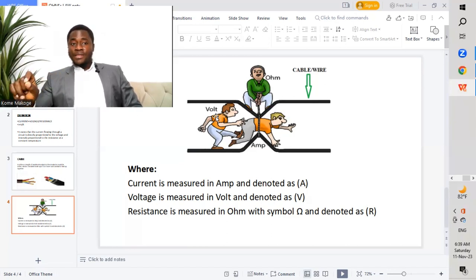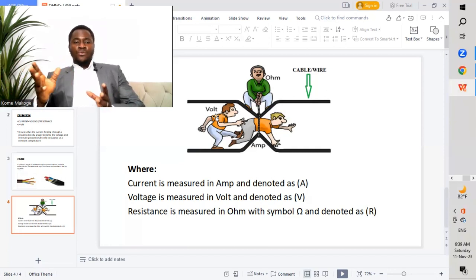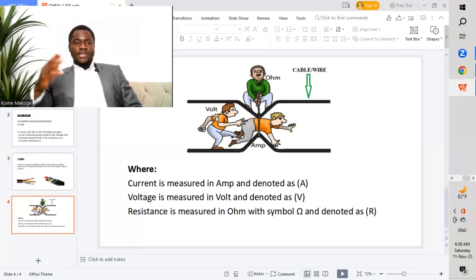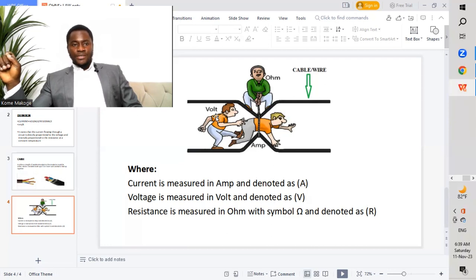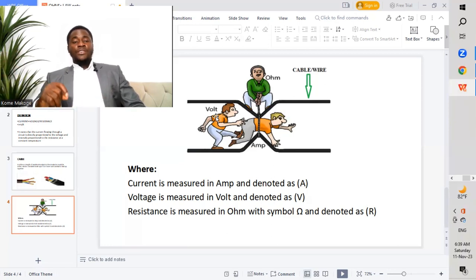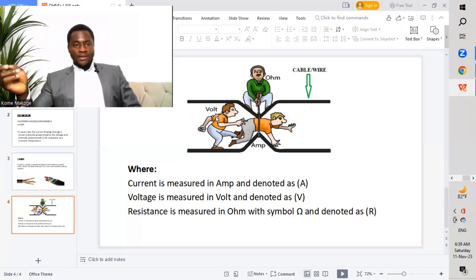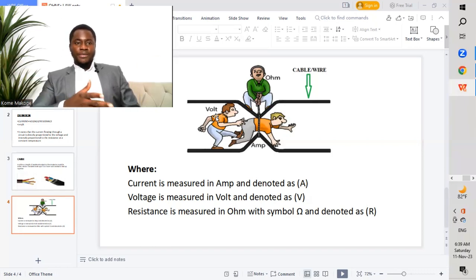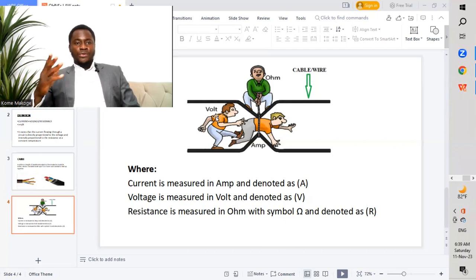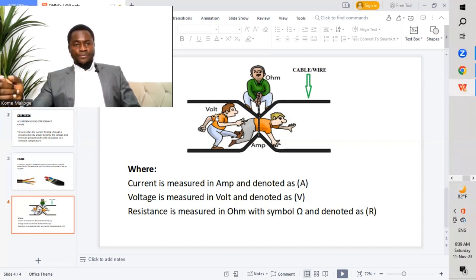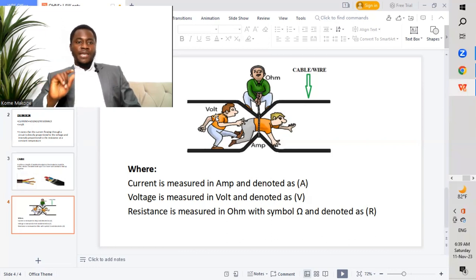Abnormality in a circuit comes in when we have a temperature rise. If you go through different cable manufacturers' catalogs, you will see different temperature ranges — either 70 degrees C or 90 degrees C. These different temperatures are taken into consideration when selecting a cable size. For example, when selecting armored cables, we might be working with 70 degrees C and we go through the appropriate column for that temperature range, selecting either copper or aluminum conductor.